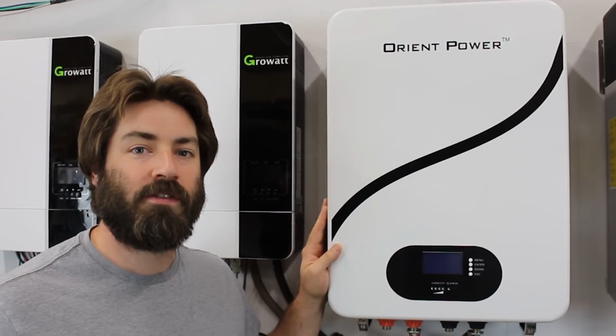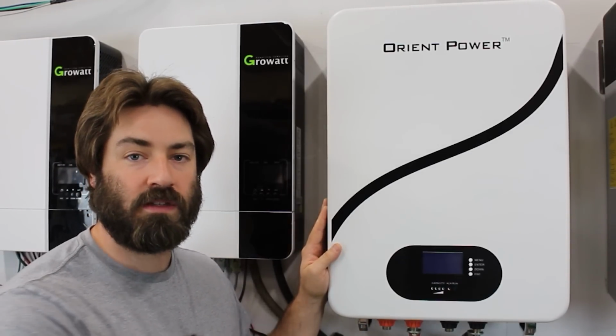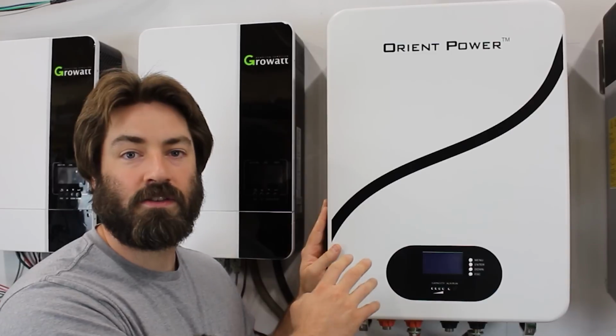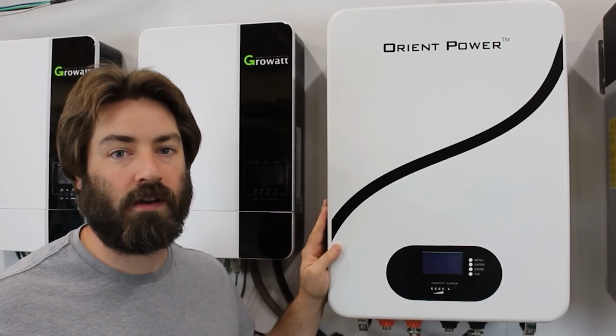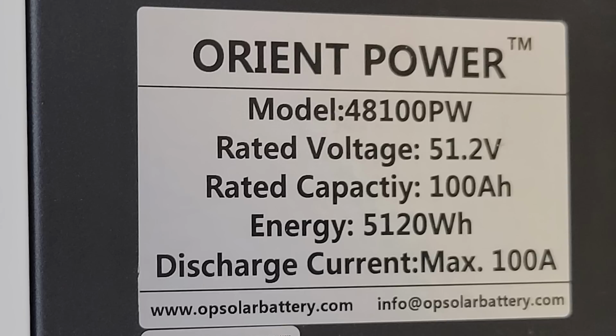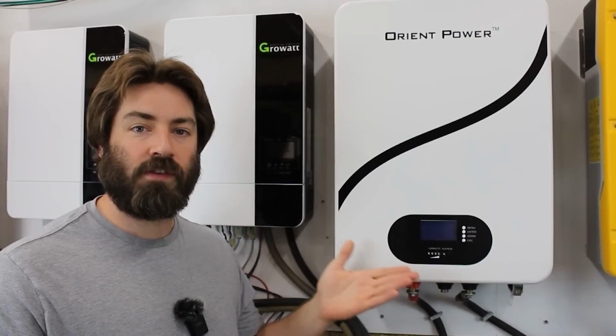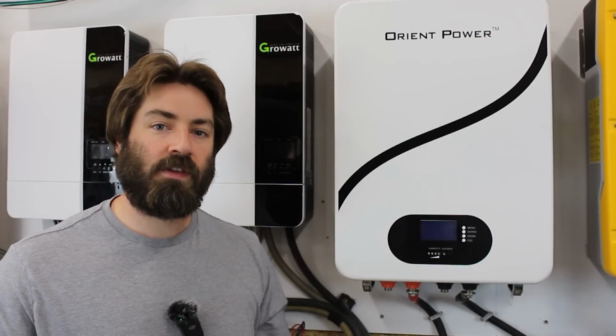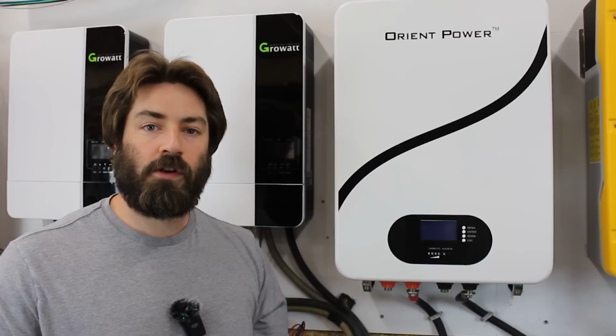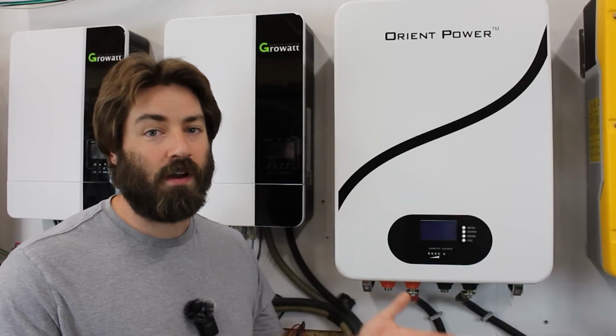Always try to keep your batteries to a half C rate, meaning you size it so you never push the battery more than 50 amps in this case, since this is a 100 amp hour battery. If you keep all your loads down to 50 amps or less, then all your equipment will last longer and run happily.